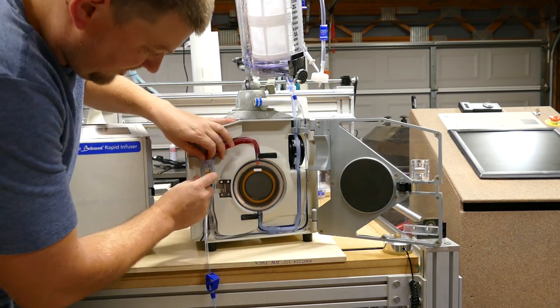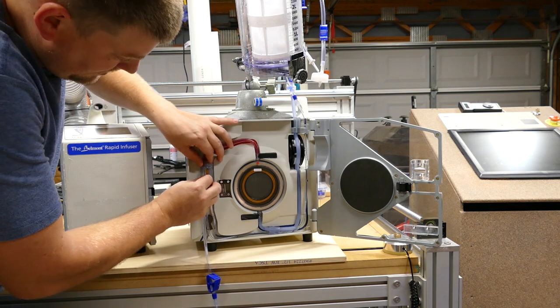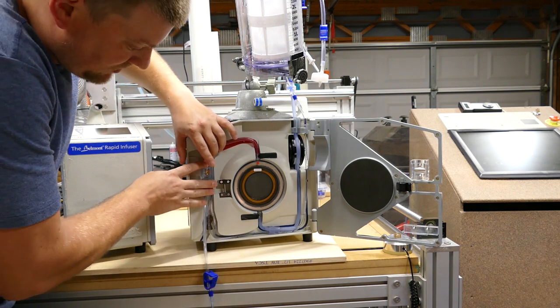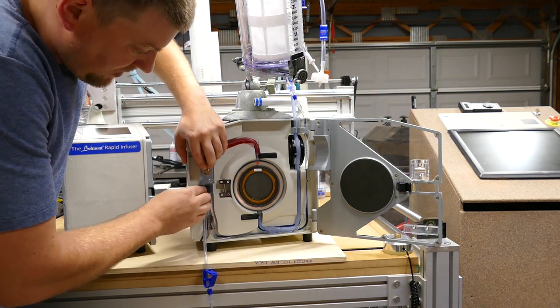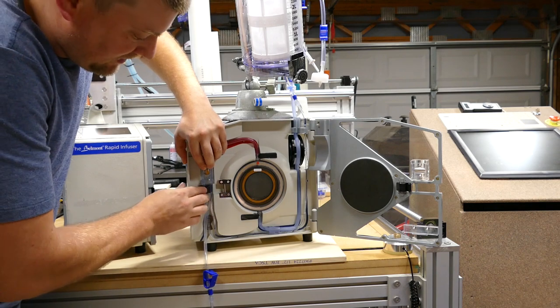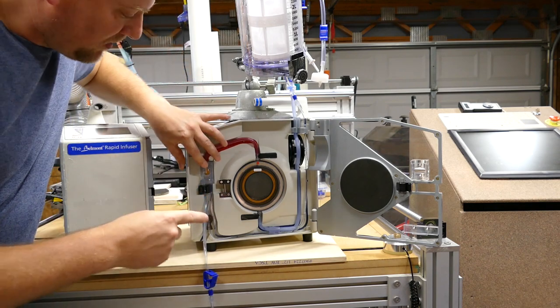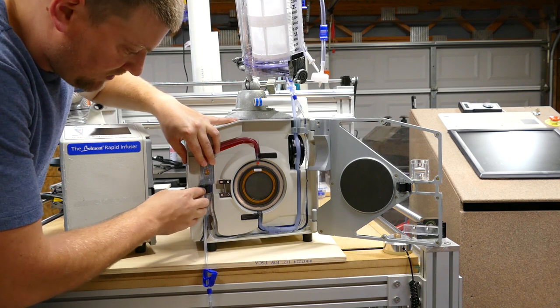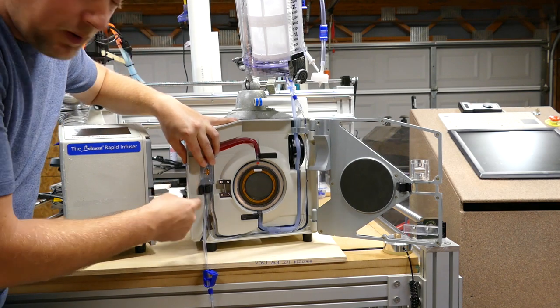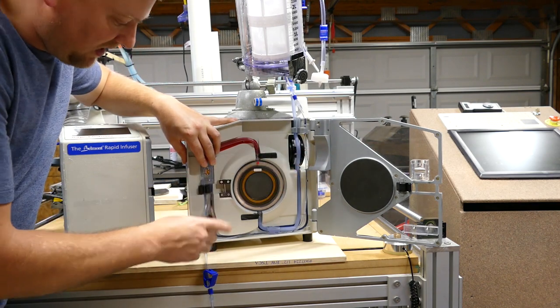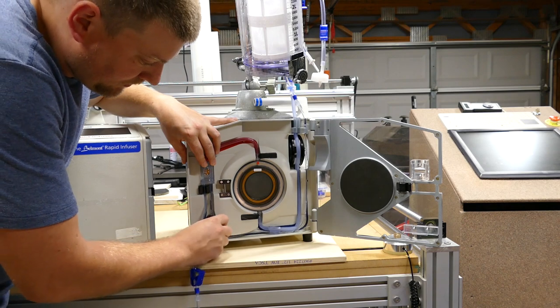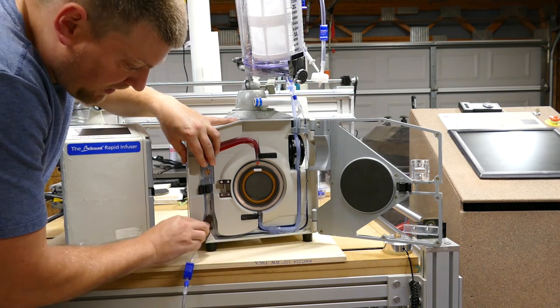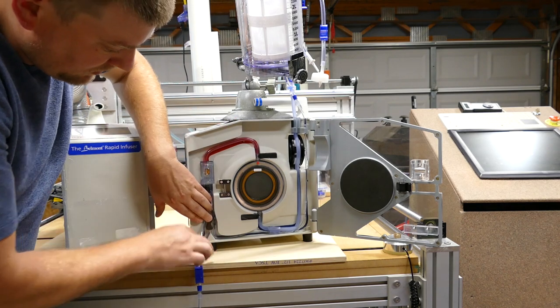Next, you're going to have your pressure chamber. It's going to press into this area. And then right below it is the air bubble detector. Now, one of the things we want to make sure is when we load a set, to press the tubing into the air bubble detector, because sometimes it can get pinched in the door. We're going to go around the pinch valve on both sides.